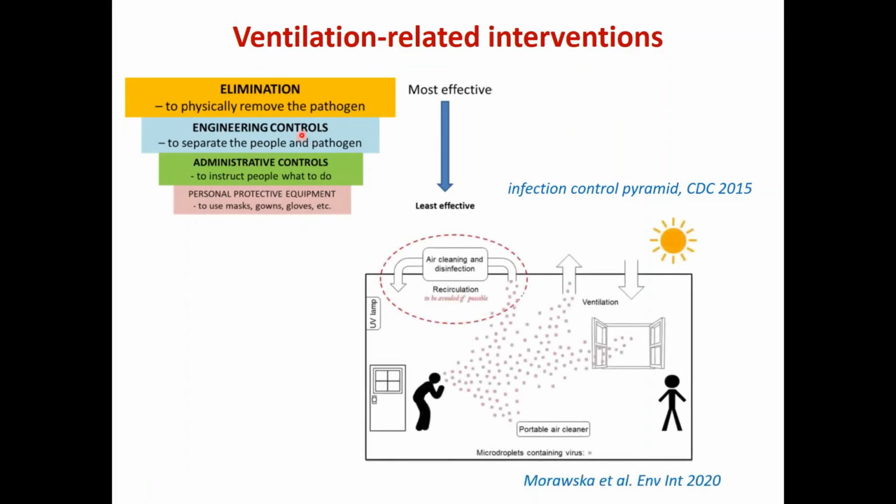Ventilation is one of them. Air cleaning is one of them. It's really having a lot of fresh air, and cleaning the air with good filtration. Very often buildings are running on recirculation systems, so there is a lot of air that is taken through the ventilation system and pushed back into the room. That's not recommended when you have these sources inside, unless you have extremely good filtration in the system, a HEPA filter, which can remove almost 100% of the particles. But otherwise, recirculation should be avoided. And if there is no other way, then portable air cleaners with effective filters could also be helpful.